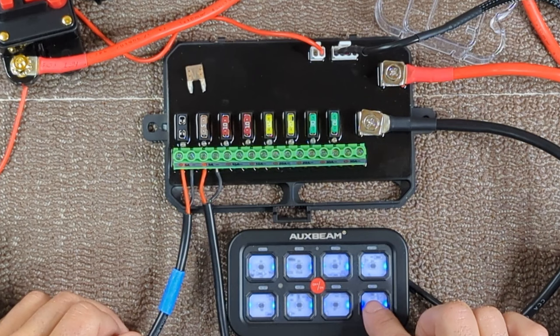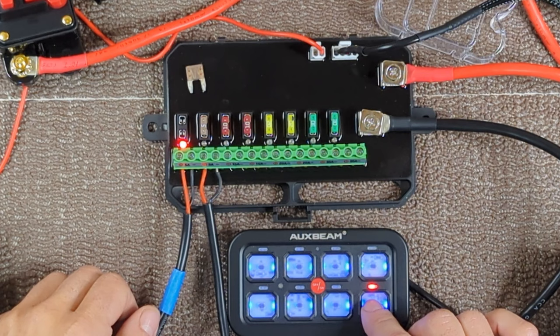If a circuit was overloaded and the fuse were to blow, a red light would illuminate. I will show you. I pulled the fuse on this circuit and I will press the button and you can see the red light is indicating that there is a break in the circuit.